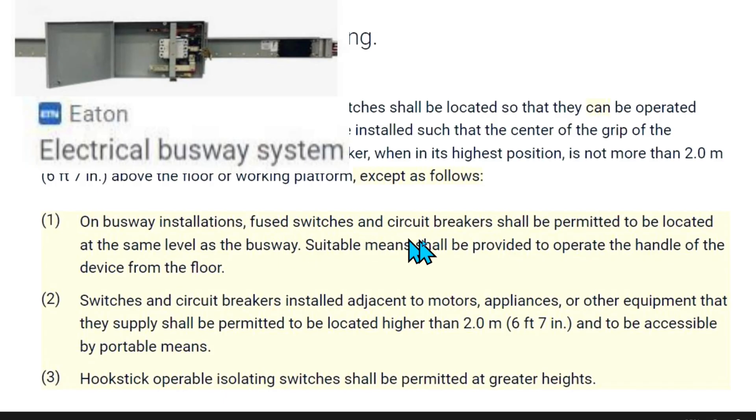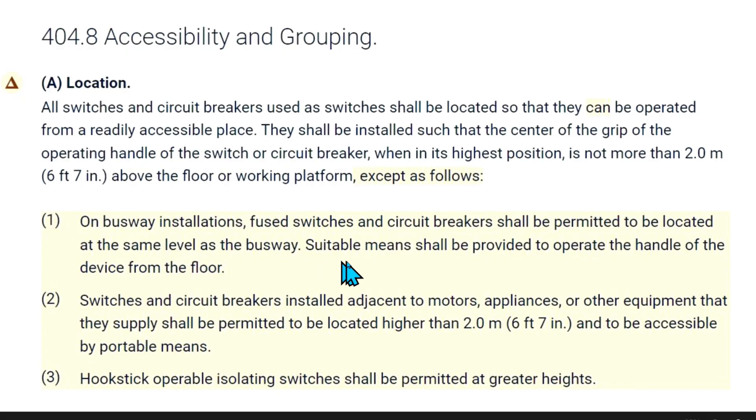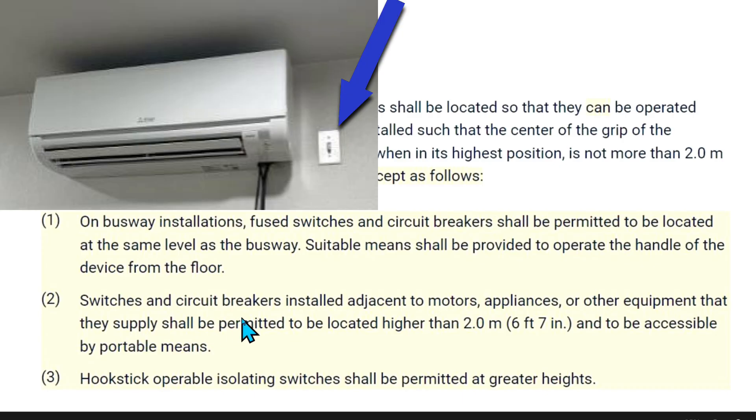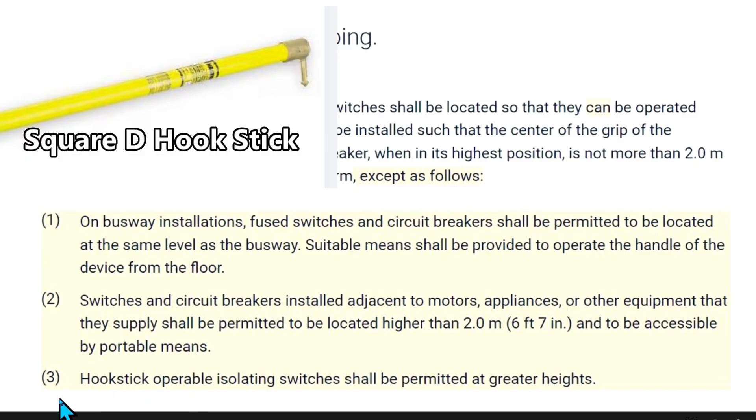You do have exceptions. One, on busway installations, fused switches and circuit breakers shall be permitted to be located at the same level as the busway. Suitable means shall be provided to operate the handle of the device from the floor. Two, switches and circuit breakers installed adjacent to motors, appliances, or other equipment that they supply shall be permitted to be located higher than 2 meters, that's 6 foot 7 inches, and to be accessible by portable means, that would be like a ladder.